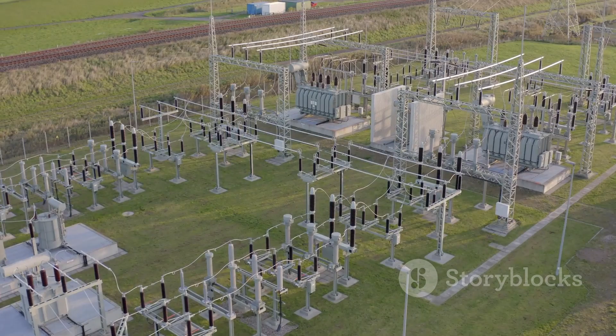But the Earth isn't a perfect conductor. Its resistance means that when a fault occurs, voltage differences, called gradients, form in the ground around the fault location. Picture ripples spreading out in a pond after a stone is thrown in. The voltage is highest right at the fault and gradually drops as you move farther away, just like the ripples fade with distance. This effect can electrify the ground near a downed power line, turning the area into a hidden danger zone. Even standing nearby can be hazardous if the voltage gradient is steep.